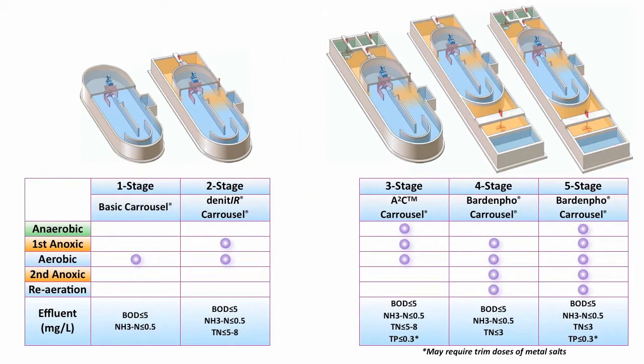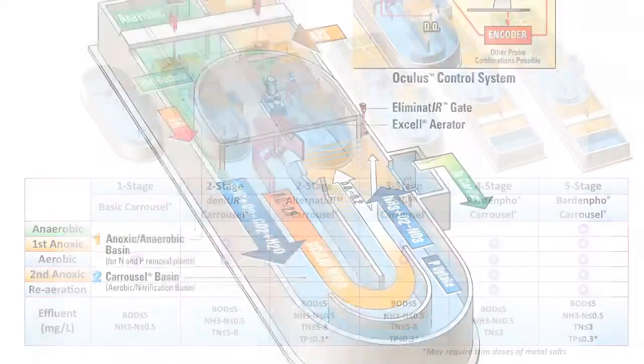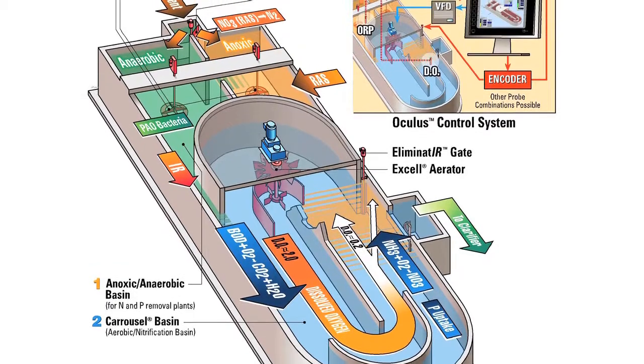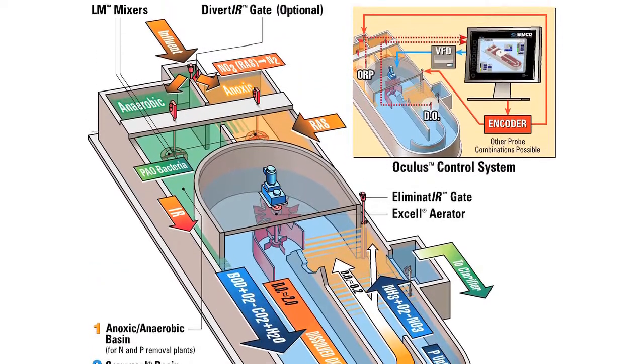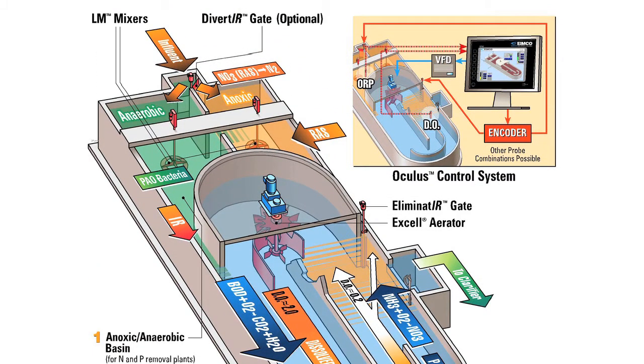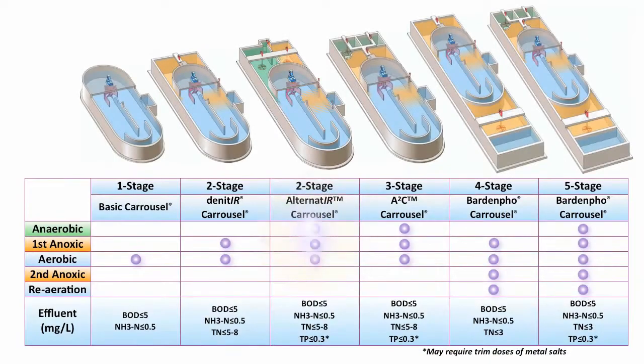New to the carousel lineup is the AlternatIR system. This 2-stage system automatically creates both anaerobic and anoxic conditions through smart internal recycle control, resulting in an effluent quality right on par with the dedicated 3-stage system. The 4 and 5 stage systems are known as Bardenpho systems. Effluent total nitrogen of 3 mg per liter and effluent total phosphorus of 0.3 mg per liter are achievable with carousel systems.